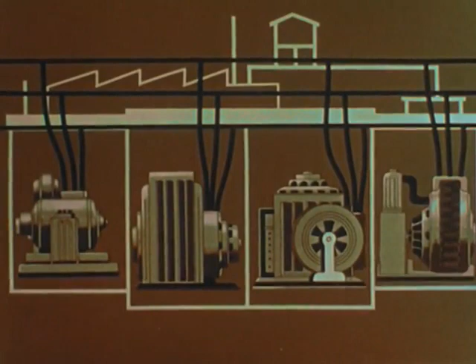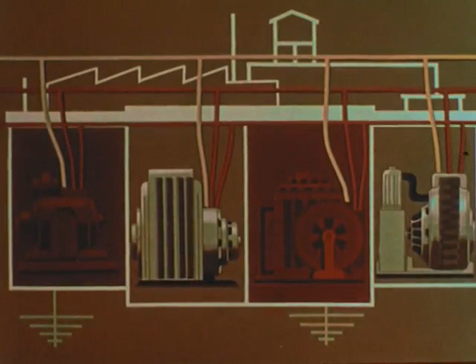The resulting strain imposed upon insulation and other equipment might, under certain conditions, lead to failure and create a second ground fault. This now means that we have a short circuit through the ground, which would undoubtedly cause a shutdown of the plant. High amperage in the system could now cause extensive damage to equipment and possible injury to operators.